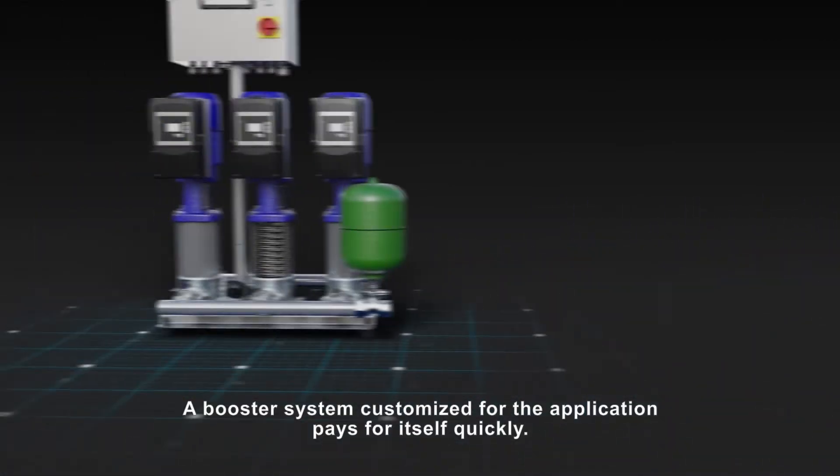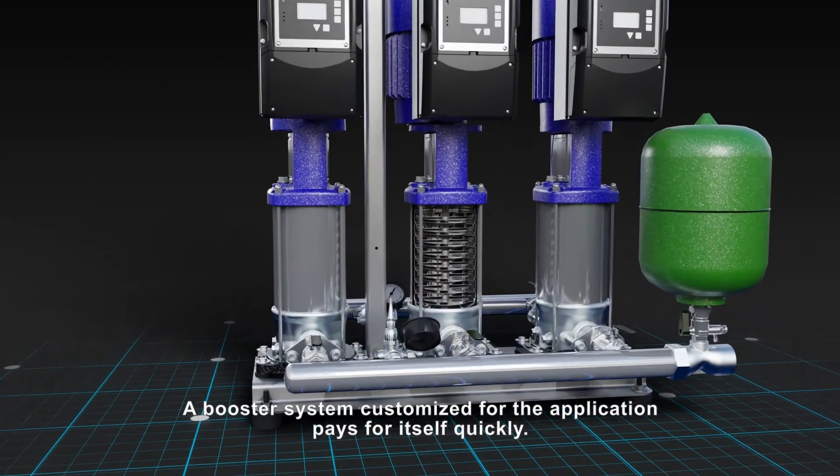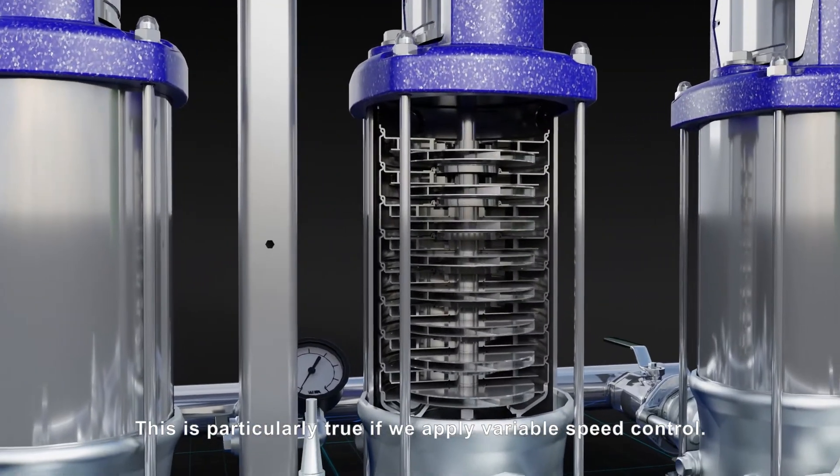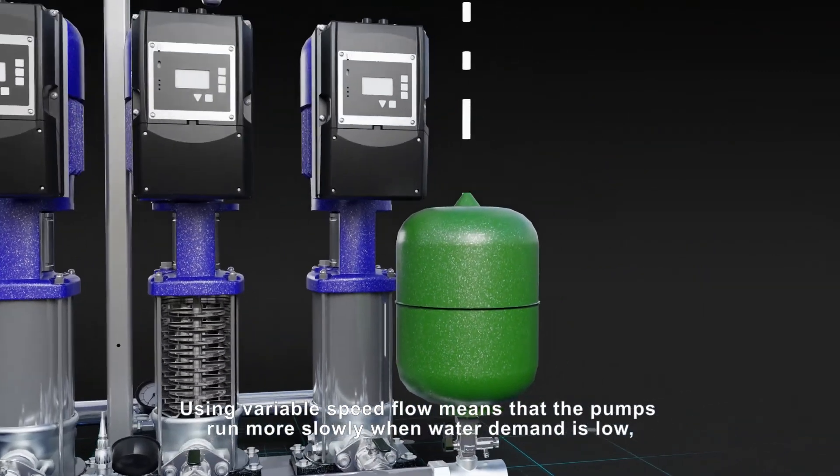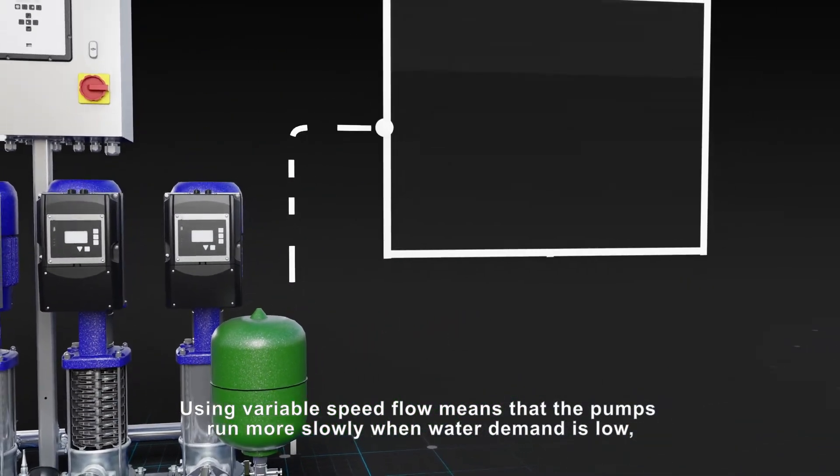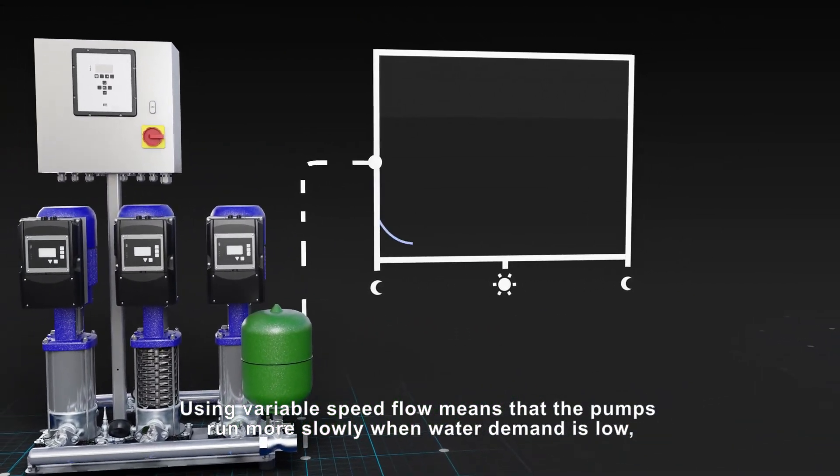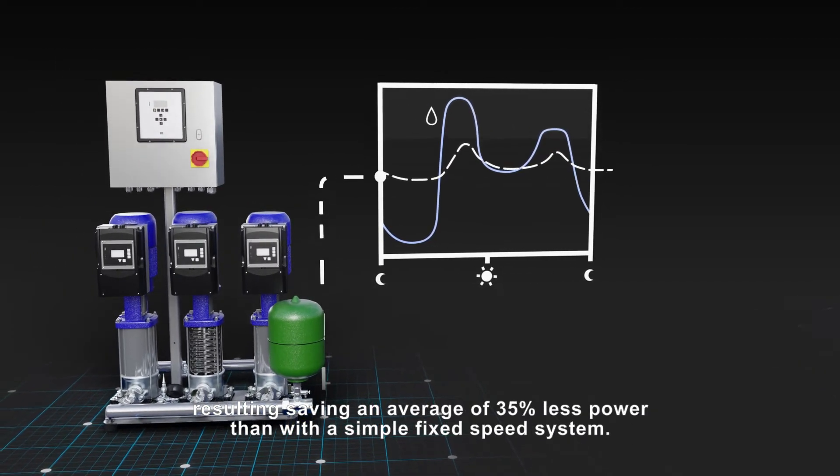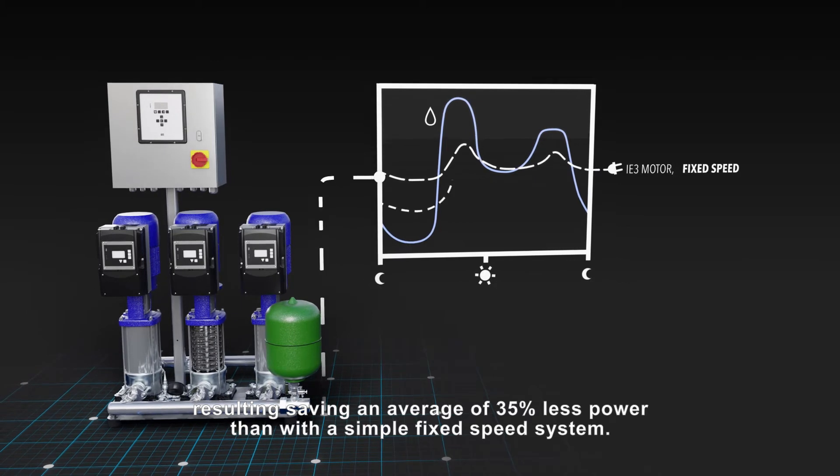A booster system customized for the application pays for itself quickly. This is particularly true if we apply variable speed control. Using variable speed flow means that the pumps run more slowly when water demand is low, resulting in saving an average of 35% less power than with a simple fixed speed system.